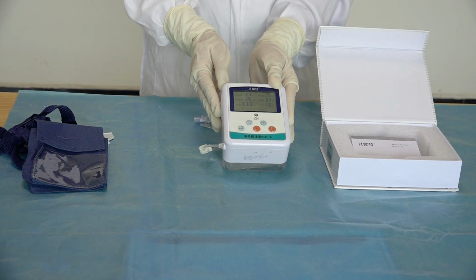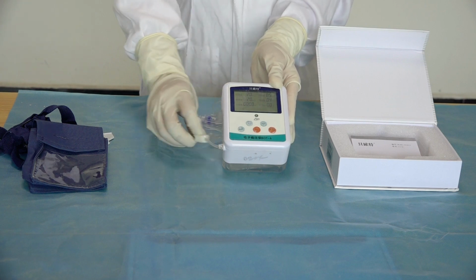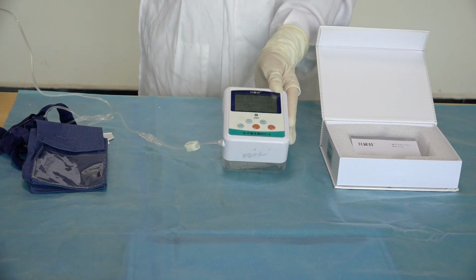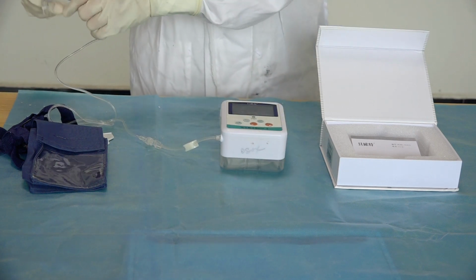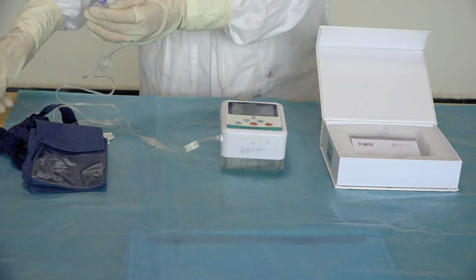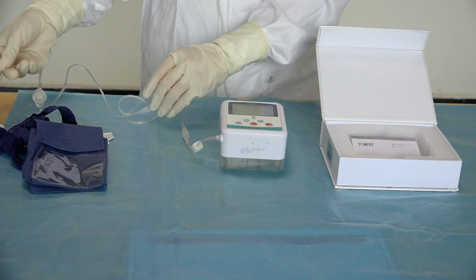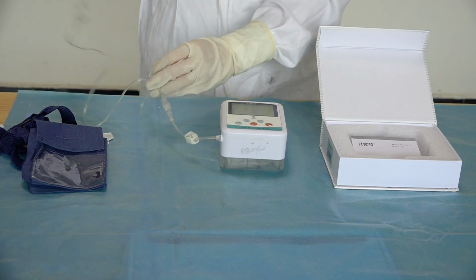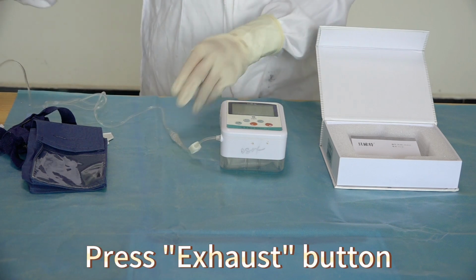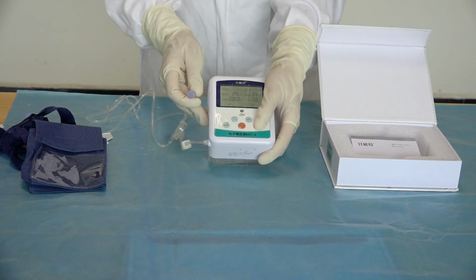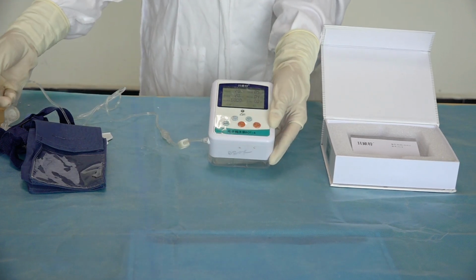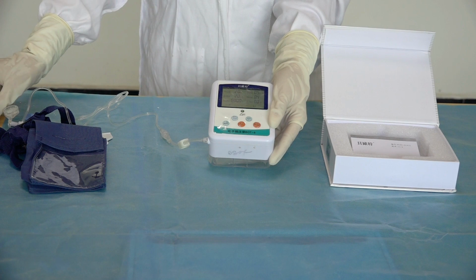Step 5. Air exhaust. Open the clamp, observe if any leakage from the liquid storage component to prevent it flow automatically. If any leakage, do not use. Press the exhaust button to exhaust the air in the liquid storage component and pipelines again to prevent remaining air.